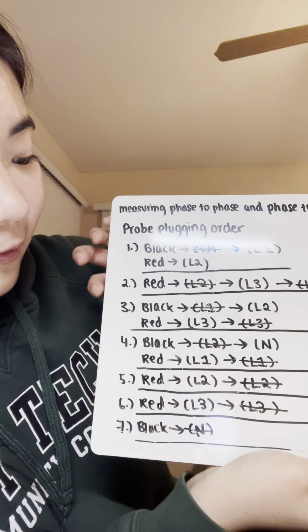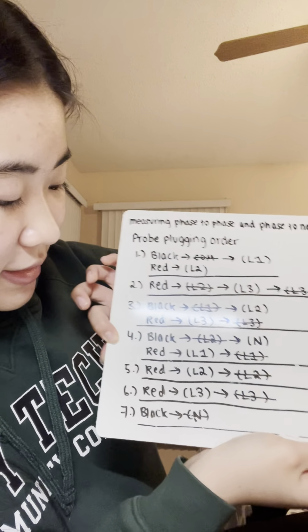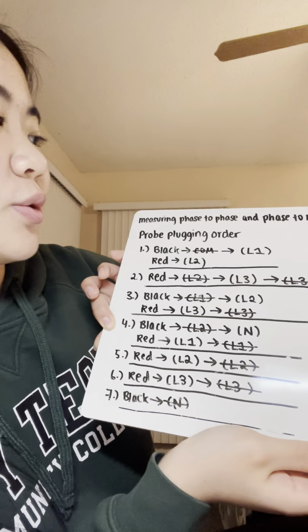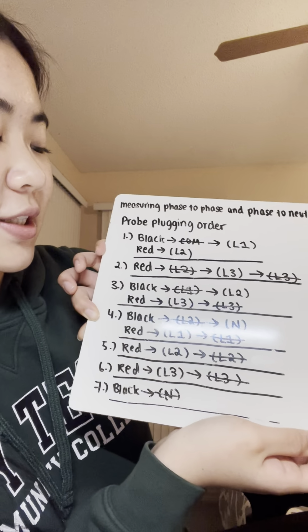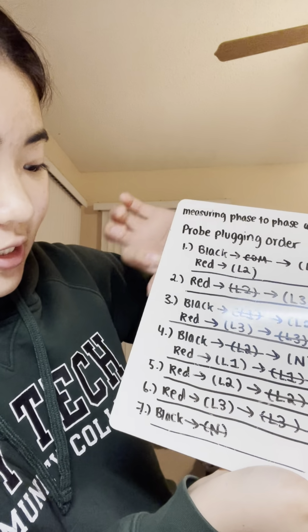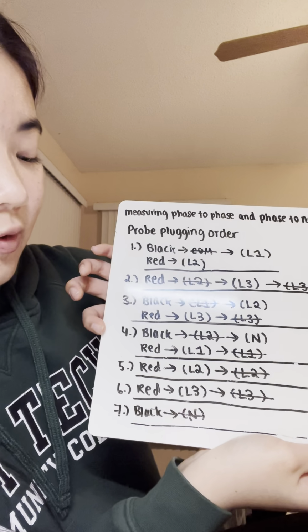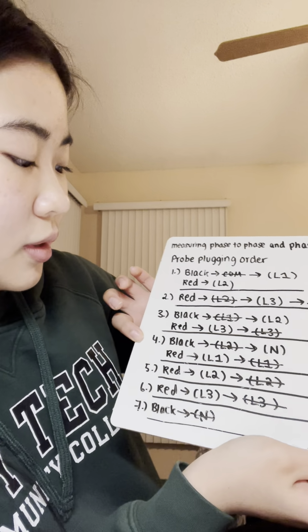Now, for the fourth section, you will be measuring phase to neutral voltage. So what you've been doing for the first 3 is measuring phase to phase; now you're moving on to phase to neutral.